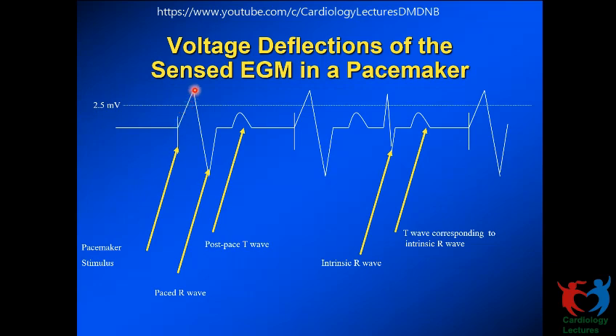It can sense the evoked R wave that comes from the pacing stimulus, which is typically very large, if I don't make any restriction for that. Similarly, it can also sense the T wave if the amplitude of that is big. We don't want to sense any of these. But yes, I want to sense the R wave if it is an intrinsic R wave, and I reset my clock based on this. So we are interested in sensing only this. We don't want to sense any of that. But if we rely only on the sensitivity setting, the pacemaker can sense all these waveforms.